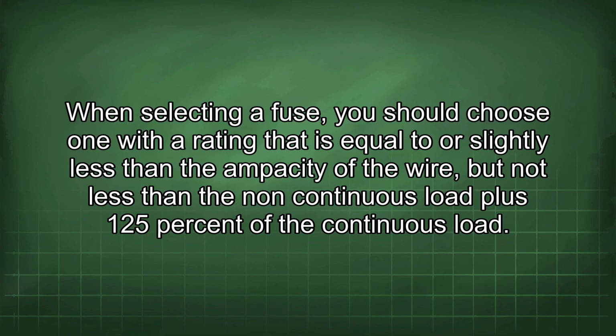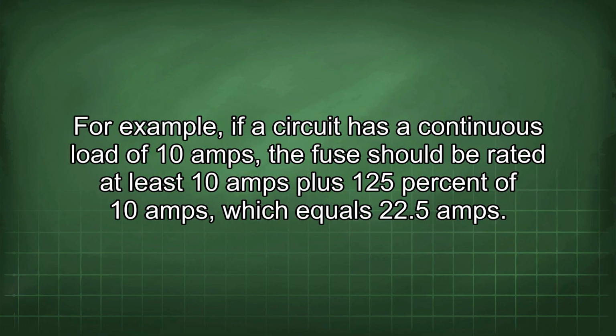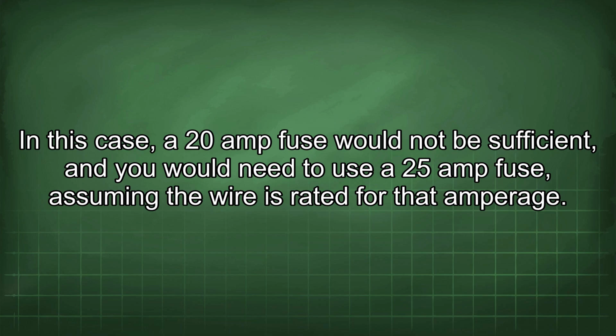When selecting a fuse, you should choose one with a rating that is equal to or slightly less than the ampacity of the wire, but not less than the non-continuous load plus 125% of the continuous load. For example, if a circuit has a continuous load of 10 amps, the fuse should be rated at least 10 amps plus 125% of 10 amps, which equals 22.5 amps. In this case, a 20 amp fuse would not be sufficient, and you would need to use a 25 amp fuse, assuming the wire is rated for that amperage.